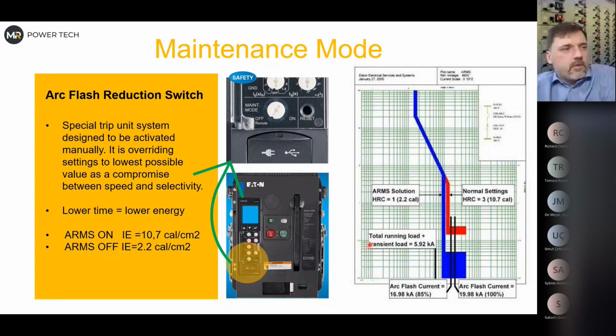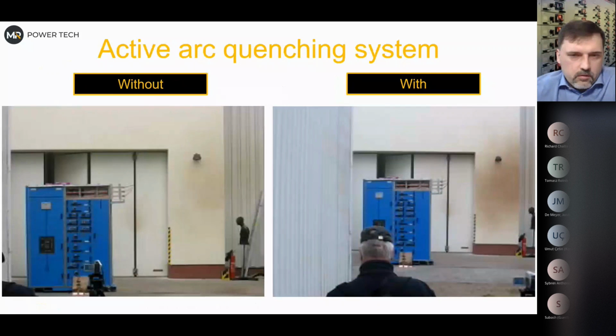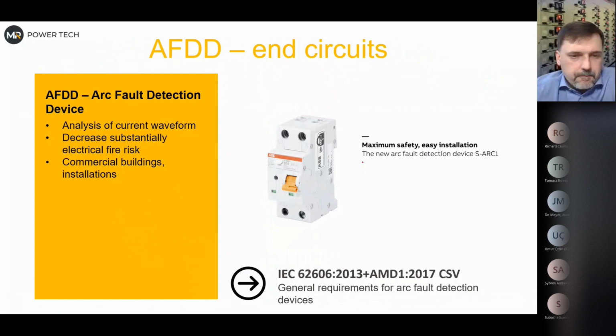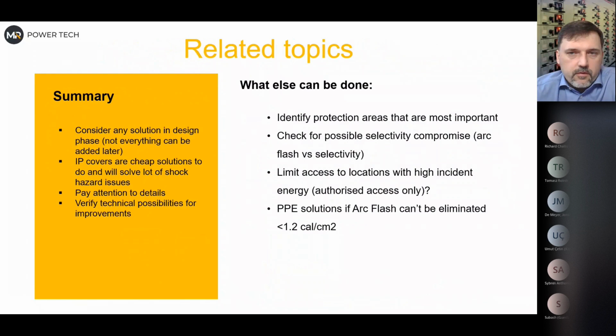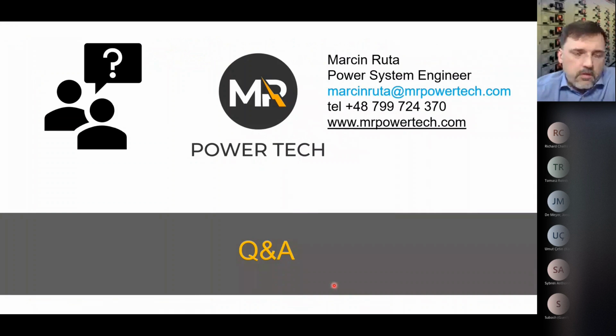Why differential protection sometimes won't be the best solution. It's not that it's not the best solution. Differential protection is a specific topic which of course costs you something. A low voltage switchgear with differential protection would be very unusual, to be honest. It's more in medium voltage systems, very often for transformers. And the point is that sometimes you have a resistor grounded system with limited current, which might be under the reach of the differential protection. So this might happen as well.